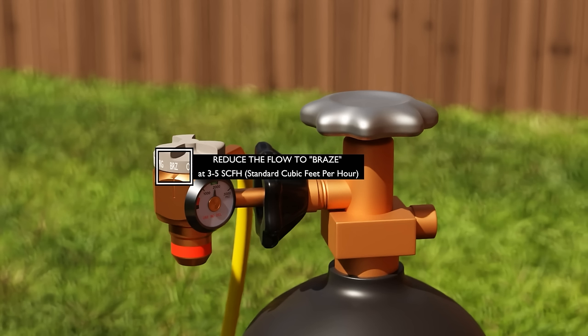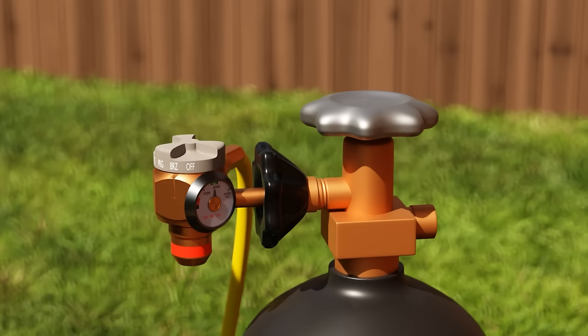Some nitrogen regulators, like the Western Enterprises regulator on this tank, have preset flow modes with a gauge to show you how many SCFH you're releasing from the tank. If you don't have a flow regulator, you can instead set a regular nitrogen regulator T-handle to a point where it's just barely whispering a flow of nitrogen. 3 to 5 SCFH is a tiny, almost imperceptible amount of flow.